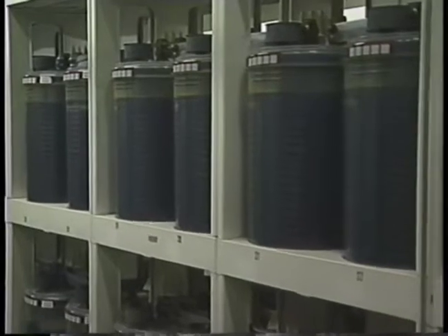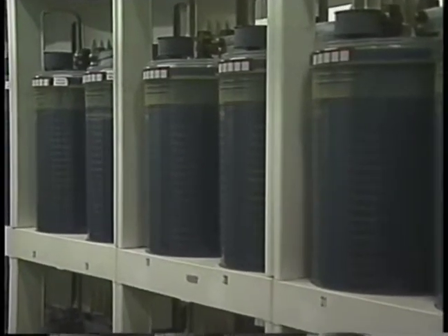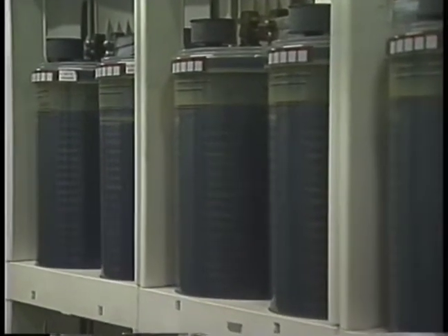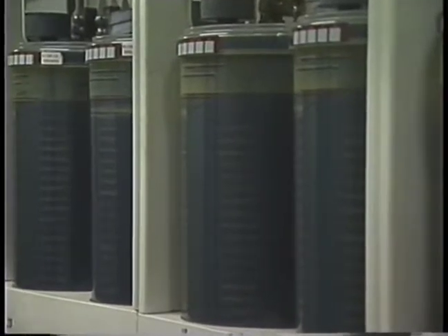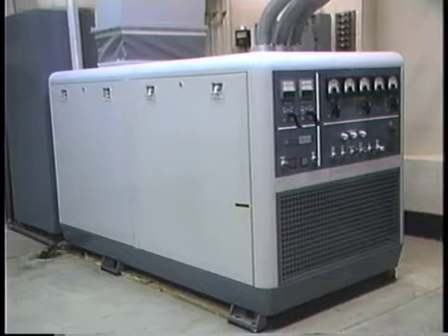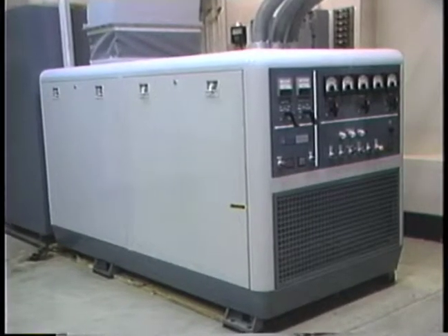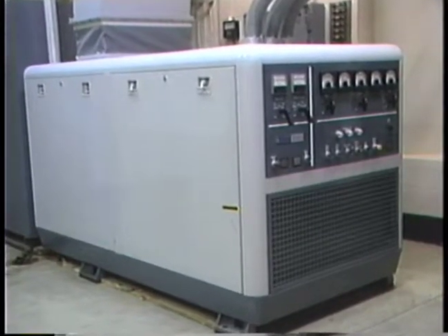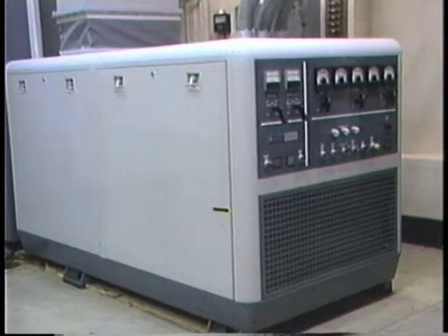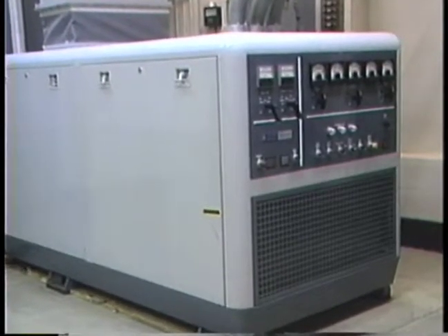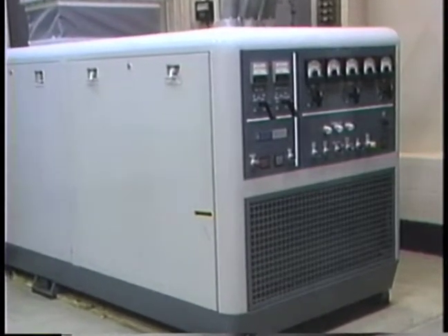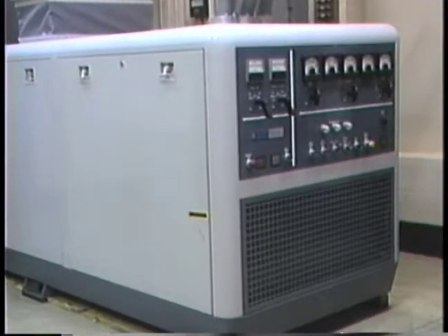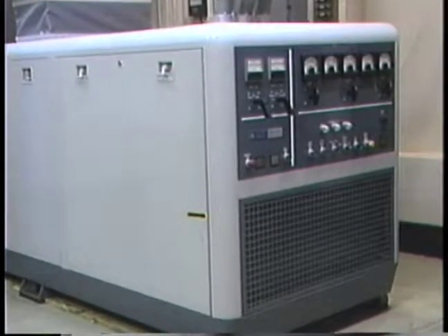When there's an electrical power failure, the batteries still supply power, but the batteries can't power this equipment for very long. Other backup power sources are generators. Many central offices have standby engine generators that start up a few minutes after an electrical power failure. The generator powers the central office and the batteries until commercial power is returned.